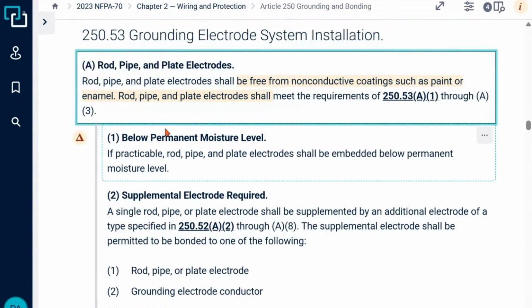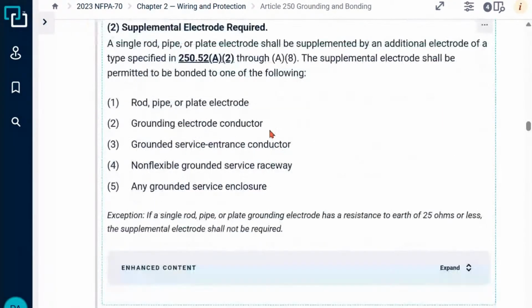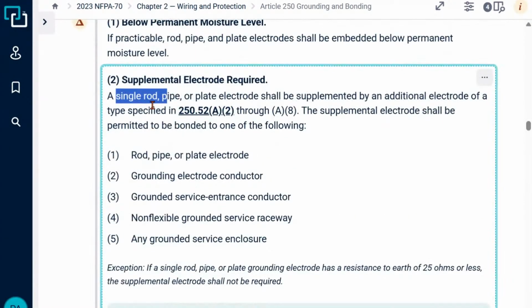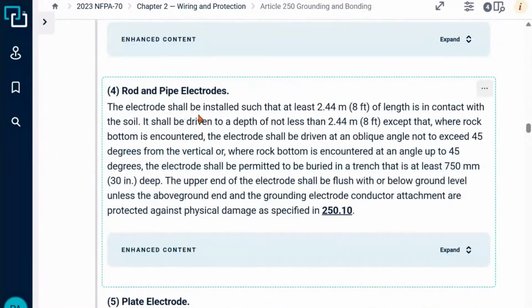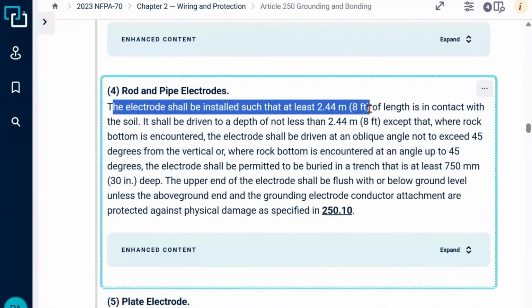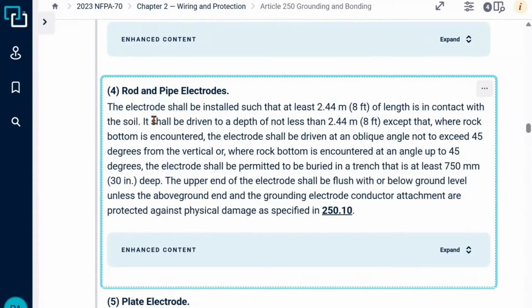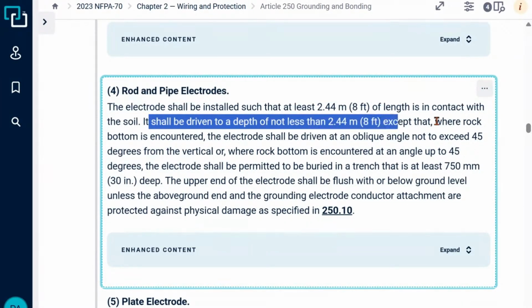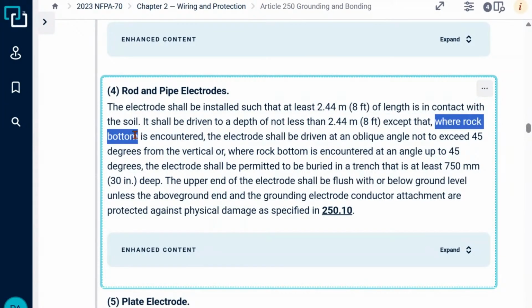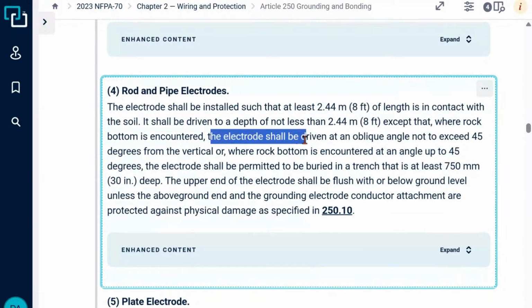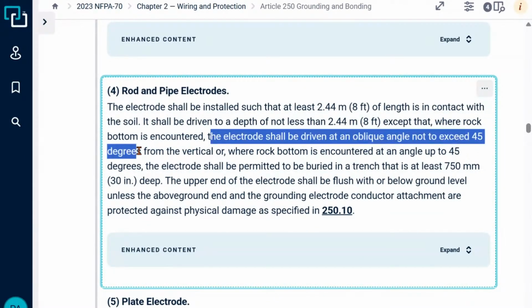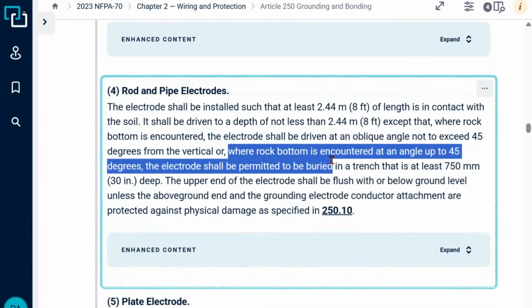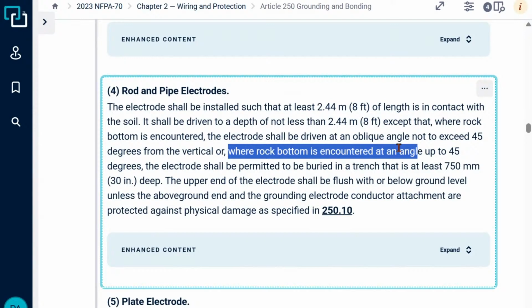If you're using a rod, pipe, or plate, by the way, here are all the requirements for it. Here's your instructions. So the electrode shall be driven at least 8 feet in length in contact with the soil. It shall be driven to a depth not less than 8 feet, except that where rock bottom is encountered, meaning you can't drive it any further. You hit rock. Then it says the electrode shall be driven at an oblique angle not to exceed 45 degrees from the vertical. So you can't get all crazy now. You can turn it up to a 45-degree angle and drive it. If you still encounter rock bottom, that's a big old rock you're hitting down there, like a boulder or whatnot.